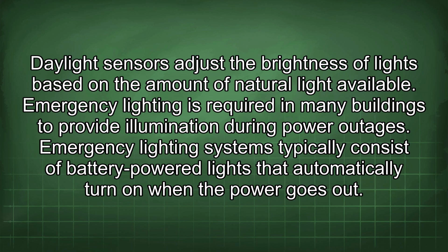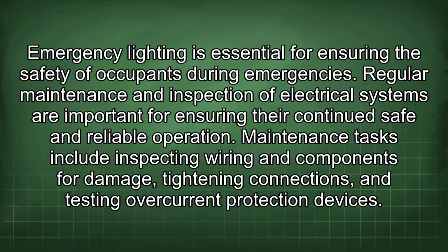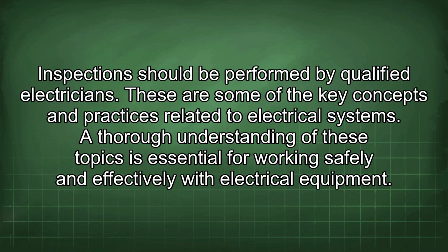Emergency lighting is required in many buildings to provide illumination during power outages. Emergency lighting systems typically consist of battery-powered lights that automatically turn on when the power goes out. Emergency lighting is essential for ensuring the safety of occupants during emergencies. Regular maintenance and inspection of electrical systems are important for ensuring their continued safe and reliable operation. Maintenance tasks include inspecting wiring and components for damage, tightening connections, and testing overcurrent protection devices. Inspections should be performed by qualified electricians.